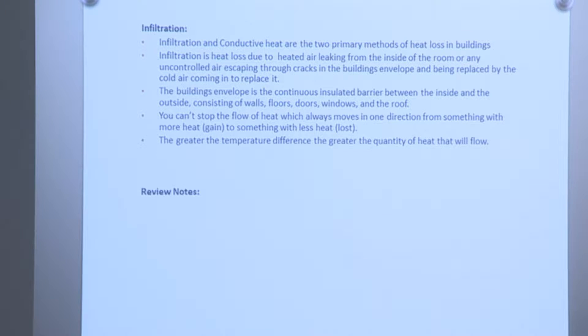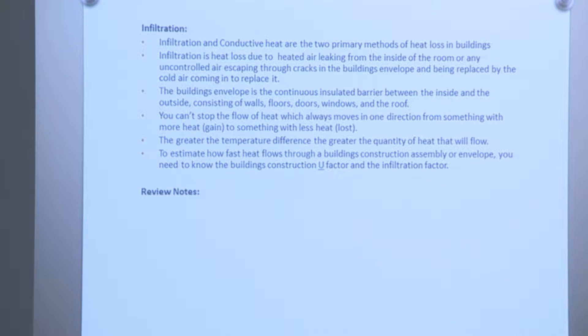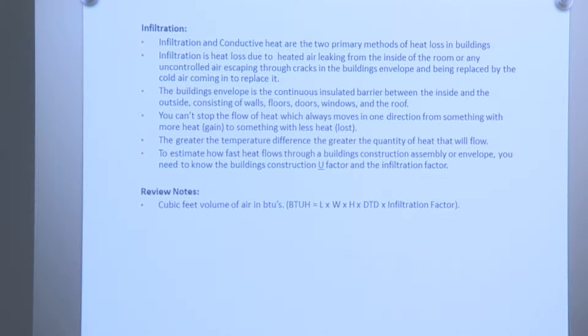You can't stop the flow of heat, which always moves in one direction — from something with more heat to something with less heat. The greater the temperature difference, the greater the quantity of heat that will flow. To estimate how fast heat flows through a building's envelope, you need to know the building's construction, U-factor, and the infiltration factor. BTUs equals length times width times height times design temperature difference times the infiltration factor.